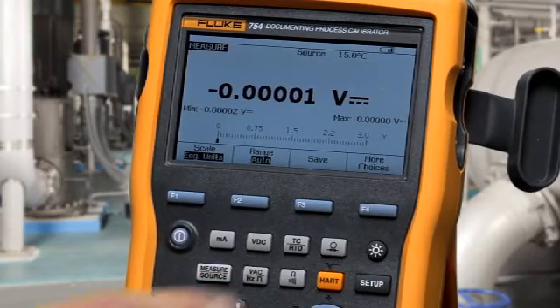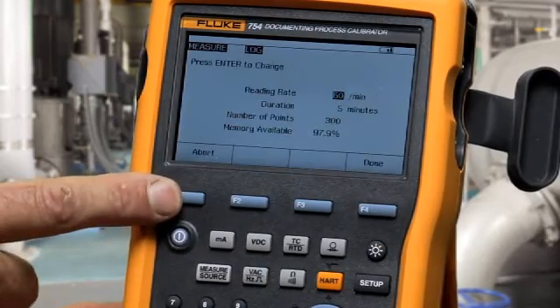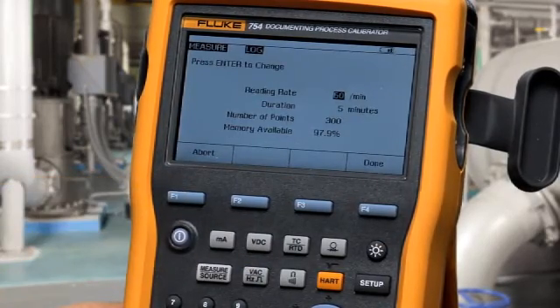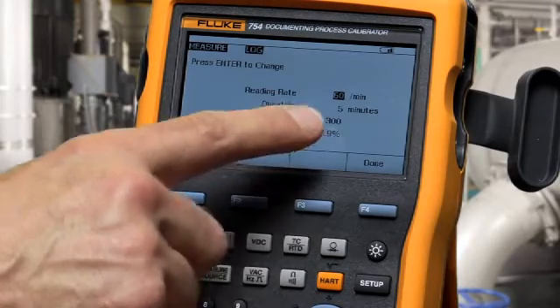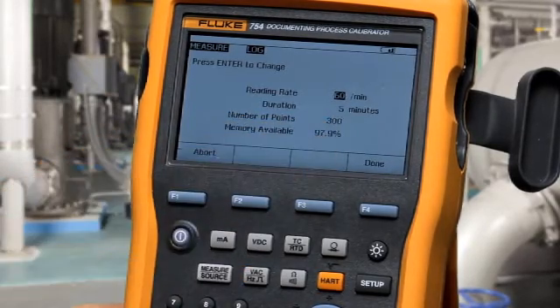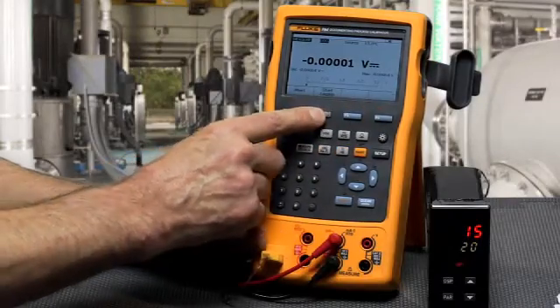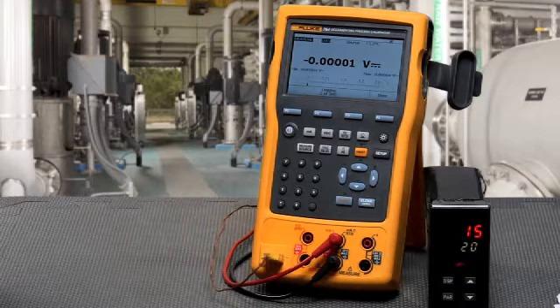To do logging measurements, select more choices and select log. Enter the reading rate that you want to log — say 60 — and the number of minutes, and that calculates the number of points based on that reading rate over that period of time. Then select done and start logging, and it will log those measurements to memory so you can upload them later to a PC. These are the troubleshooting features of the Fluke 753 and 754 calibrators.